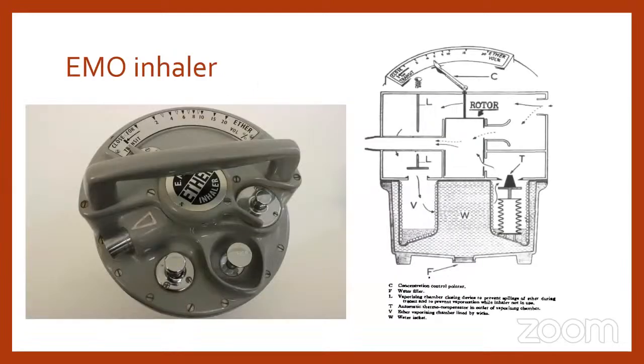And the next one is the EMO vaporizer. It is basically the Epstein, Macintosh, and Oxford inhaler. It is a variable bypass, concentration calibrated, draw over or flow over type of vaporizing technique. It is agent specific and it is labeled over here. Ether is the major agent which is used in this. The temperature will be compensated, and this vaporizer is incorporated within the circuit, so the flow will not be disturbed. Used for controlled and spontaneous ventilation.